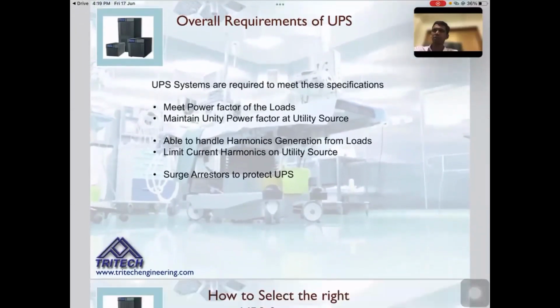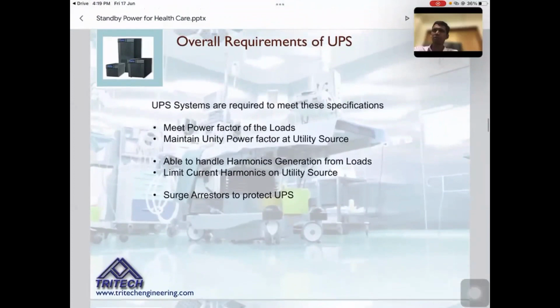This slide explains why a UPS system is required, and overall considerations for selecting a UPS. So the primary thing is it should meet the loads, and it should meet the power factor of the loads, and it should also maintain the power factor at the utility source, which means irrespective of whatever load is connected to the UPS, it has the ability to correct the power factor at the input side. So basically, maintaining this will be helpful for many of the problems related with low power factor.